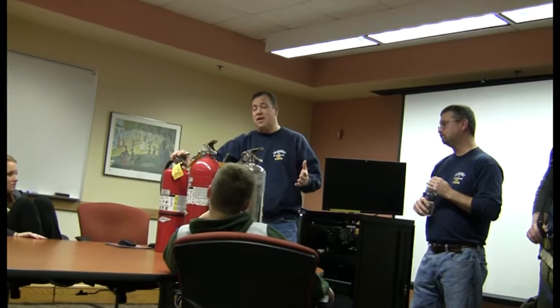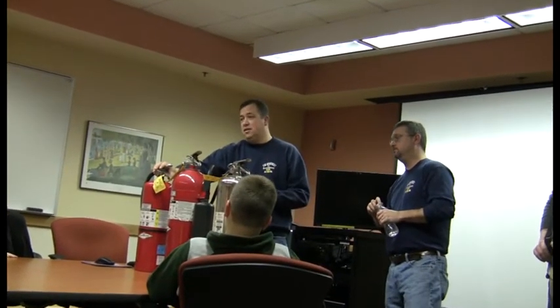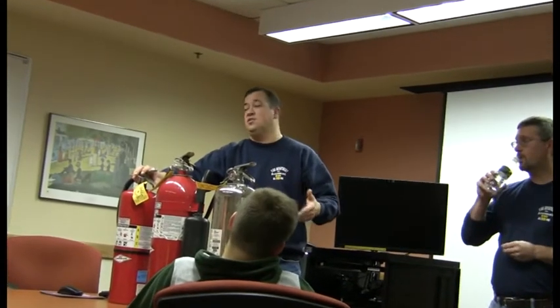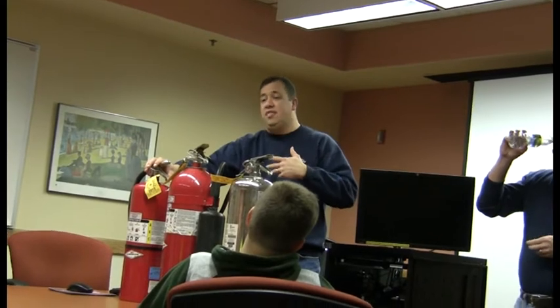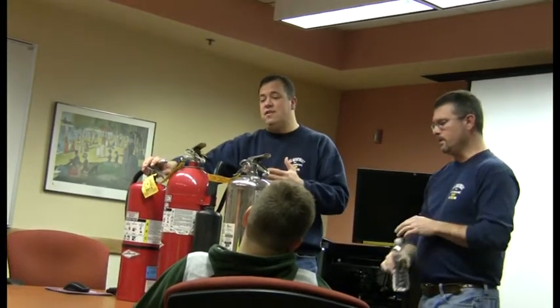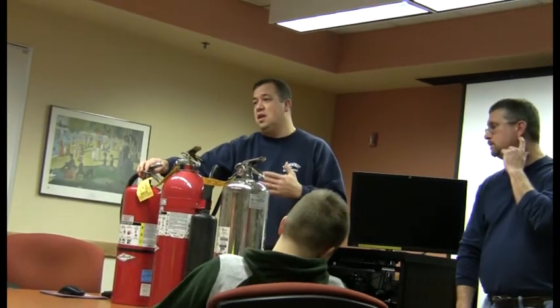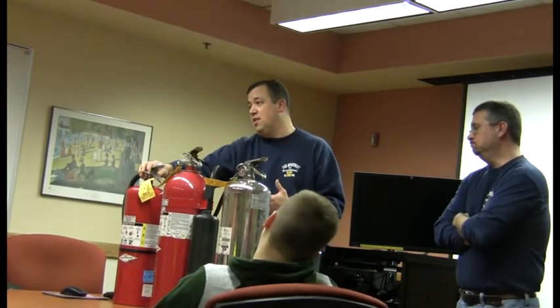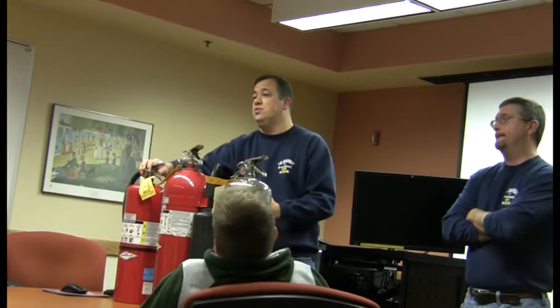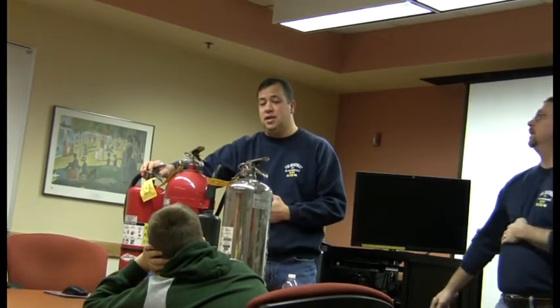So if you, let's say, have a trash can on fire or a small computer fire, use them for that. If it has gone further than that, where the trash can is now on fire and it's going up the wall and across the ceiling, that is not a fire that you should attempt to fight. Even if you find a fire, activate the fire alarm first, pull a pull station, tell somebody, call 911, and then attempt to put the fire out. But you want to give your peers, your co-workers, your student body, time to get out of the building and be safe when they exit the building.